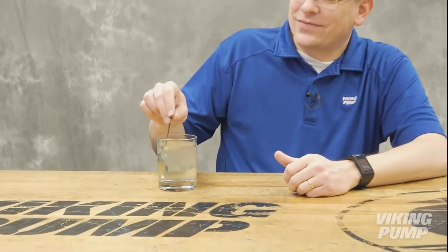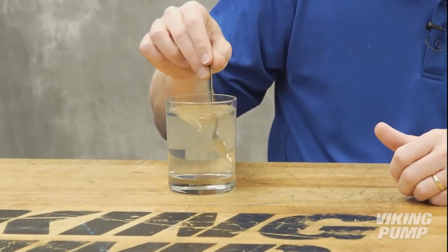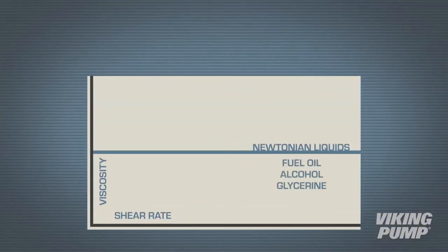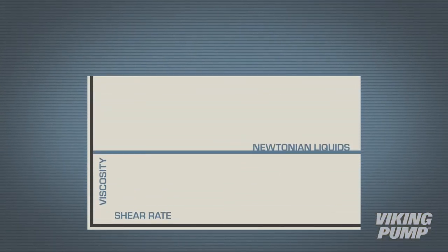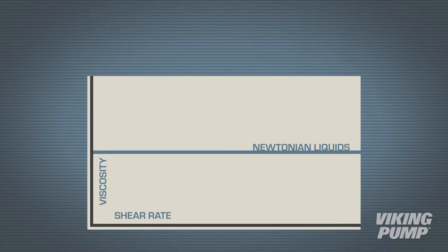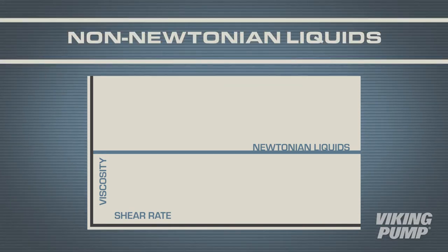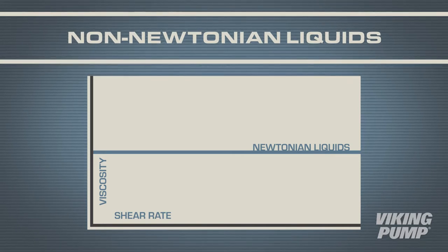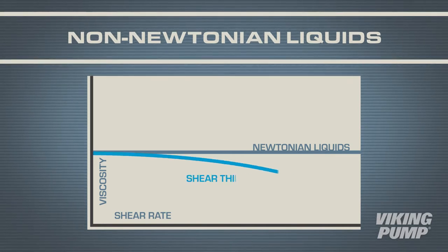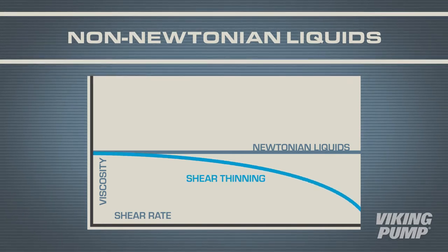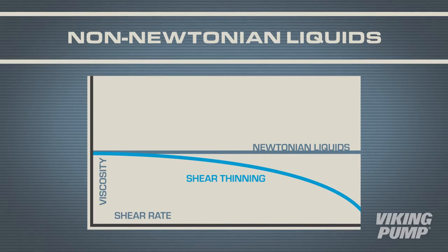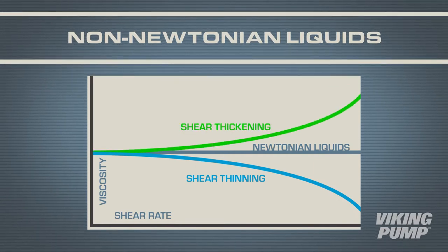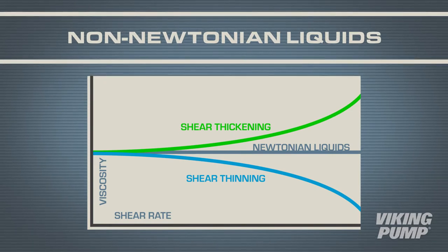Water retains its viscosity independent of the rate of shear. Other examples include fuel oil, alcohol, and glycerin. The majority of Viking pump applications fall into a second category of non-Newtonian liquids. While there are a variety of each, let's keep this fairly simple. Some liquids decrease in viscosity as shear is applied — these are shear thinning liquids. Another class of non-Newtonian liquids increases in viscosity as shear is applied — these are shear thickening liquids.